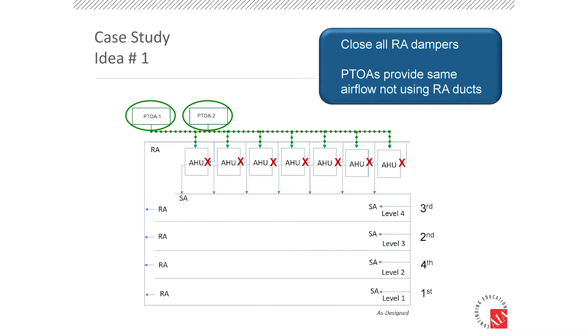This is probably the only math in the whole presentation: each air handler does 26,000 CFM, for a total of 182,000. My PTOAs could only supply 60,000. So what that meant is I'm short about 122,000 CFM to feed the floors, which is fine, except it's not great for your building to be overpressurized by 122,000 CFM.